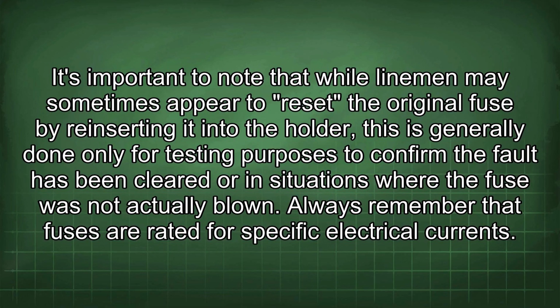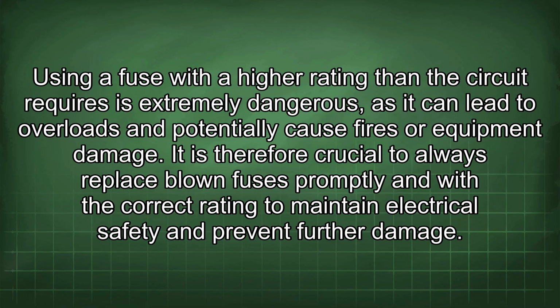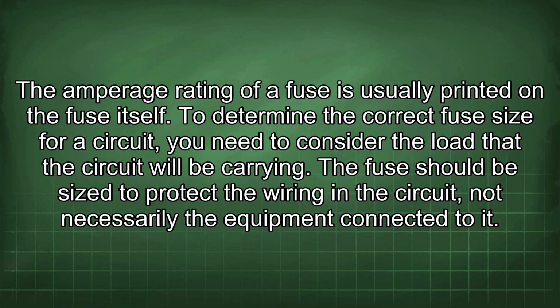Always remember that fuses are rated for specific electrical currents. Using a fuse with a higher rating than the circuit requires is extremely dangerous, as it can lead to overloads and potentially cause fires or equipment damage. It is therefore crucial to always replace blown fuses promptly and with the correct rating to maintain electrical safety and prevent further damage. The amperage rating of a fuse is usually printed on the fuse itself.